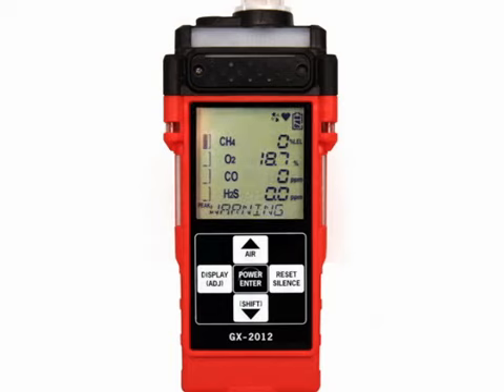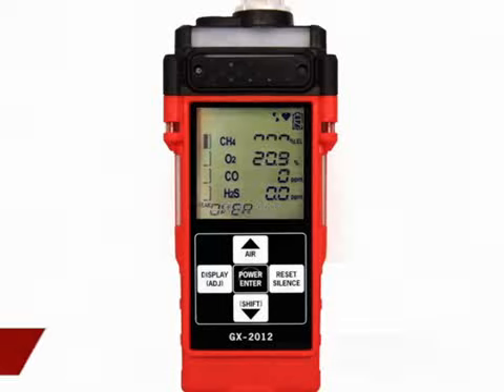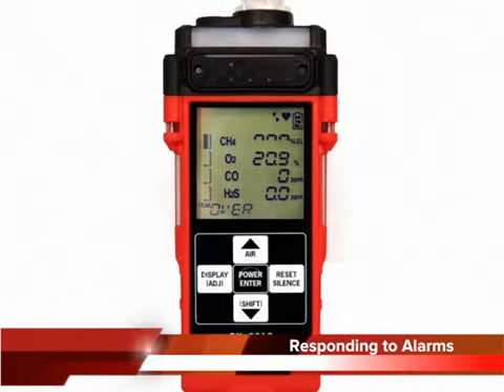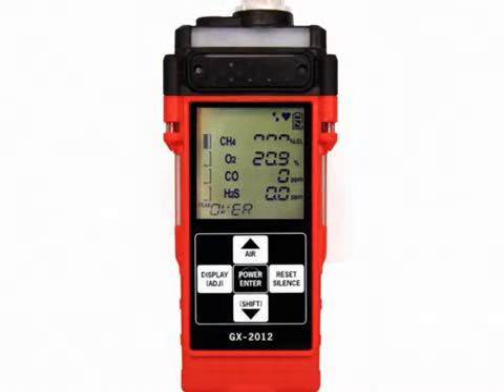With alarm silence set to off in maintenance mode, you cannot silence the buzzer while the gas reading is beyond the low alarm setting. An overrange condition may indicate an extreme combustible gas, toxic gas, or oxygen content condition. Take immediate action and confirm the gas levels in the area with a different GX-2012 or with another gas detecting device. Determine which gas alarm has been activated.